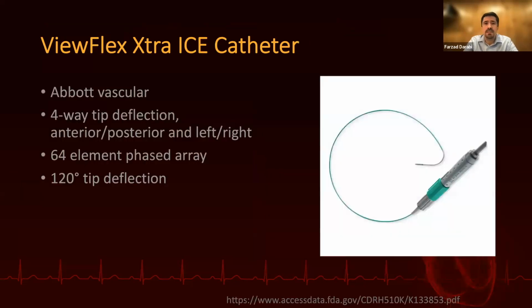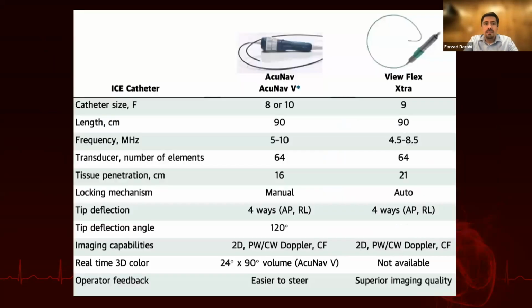The other company who has a comparable device is St. Jude, which is now owned by Abbott. It's also a 4-way catheter, 64 elements, similar to the AcuNav, and we use this one in the cath lab at St. Michael's as well. To compare these two probes, they are basically similar. One of them is 9 French, the other has 8 and 10 French. Both use similar frequencies, similar type of transducer, with relatively the same tissue penetration. However, tissue penetration in the ViewFlex Xtra is a bit longer and it had superior image quality, but at the same time, it doesn't have the 3D capabilities that AcuNav has.